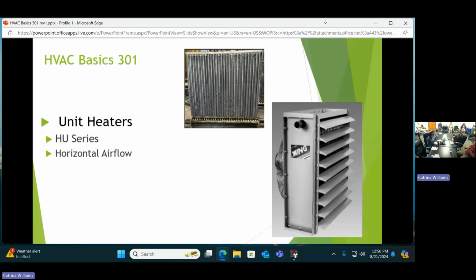Here's our HU series. And as you can see in this picture on the right-hand side, it's a simple unit made for horizontal airflow, fan in the back, blowing across the coil, and putting air into the space. And I want to point out the picture of this coil up on top, how that's just a straight, what I'll call slab coil, compared to what Doug was explaining with the space in between them for the bypass. You no longer need that bypass. So it's just a straight heating coil now. Very simple.